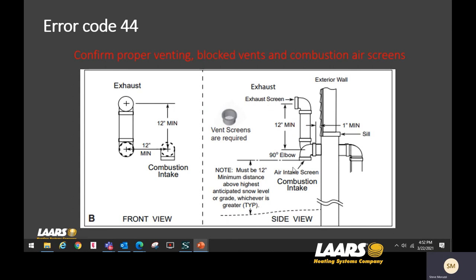In our manual we have installations for sidewall venting, roof venting, and more. For sidewall venting, the combustion air intake is always below the exhaust. Run a 90 to combustion air down, and on the exhaust you can come up in a gooseneck — minimum 12 inches — and then 90 straight out away from the dwelling. Never 90 back down, because flue gases would travel down and get drawn right back into the combustion air intake. Minimum 12-inch horizontal separation: combustion air intake comes out, 12 inches away is the exhaust, with a minimum 12 inches up before exiting the dwelling.